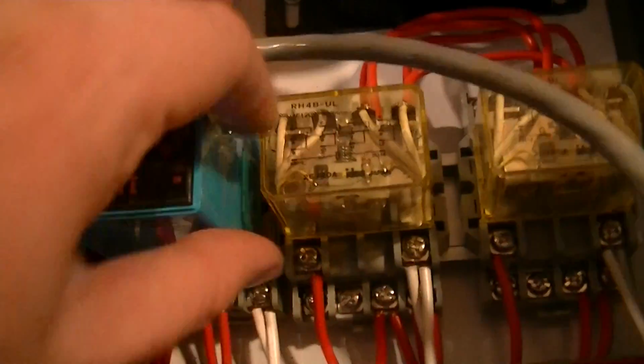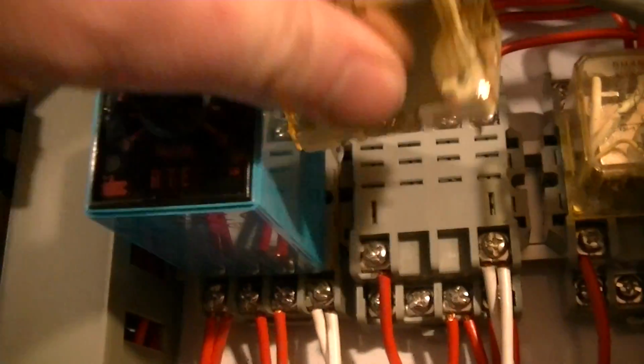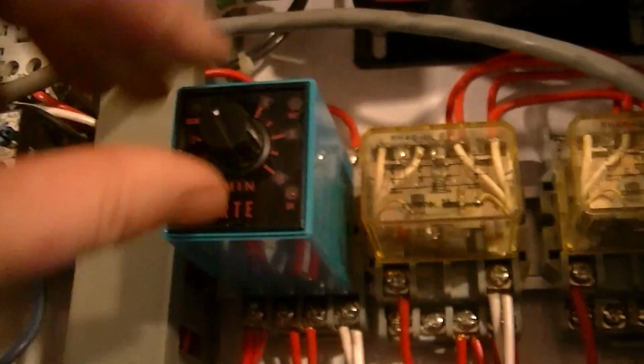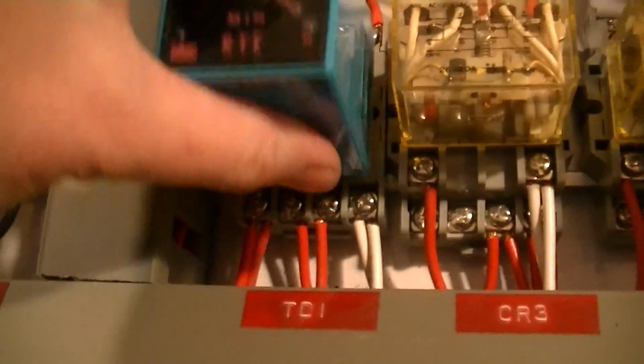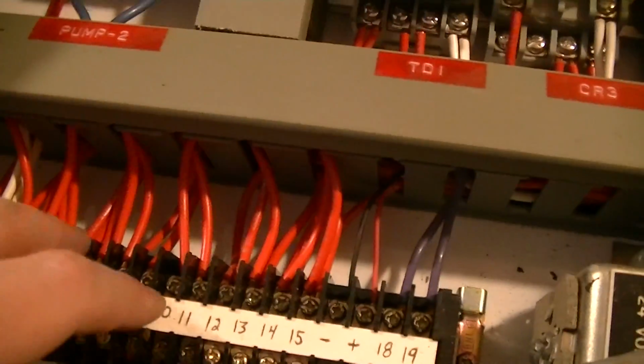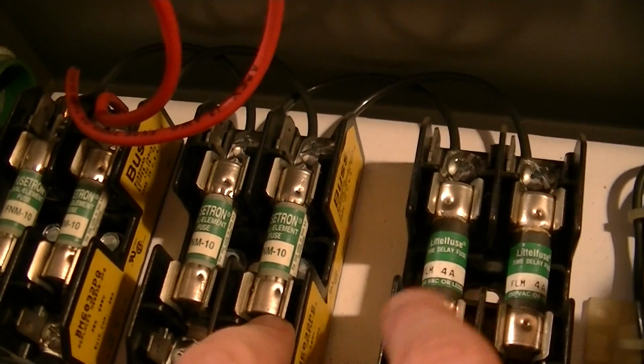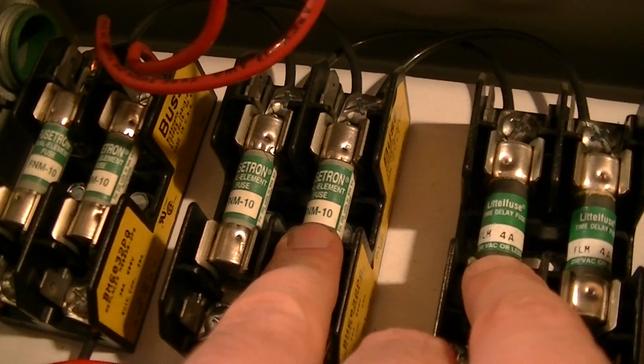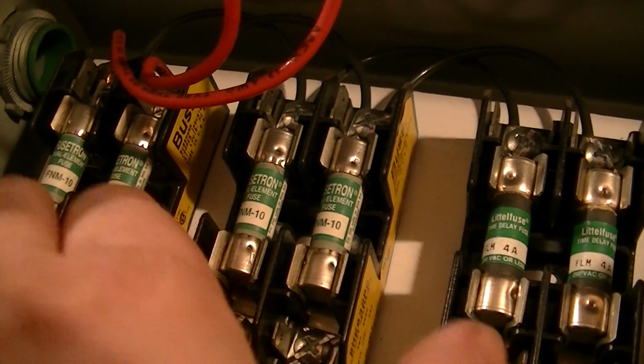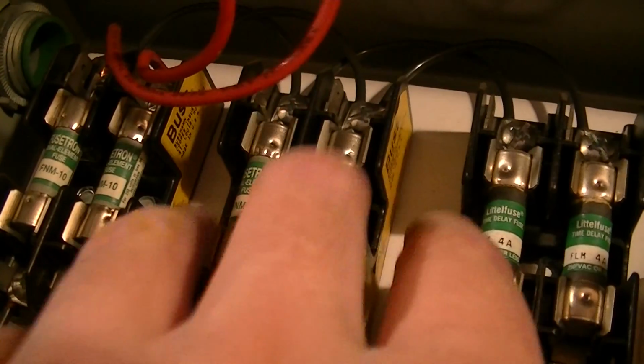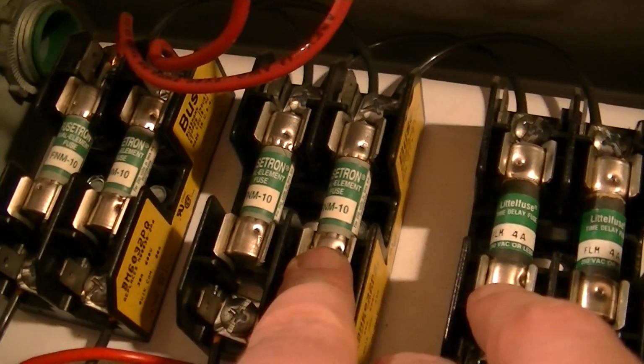And then of course there's a pair of regular, conventional 4-pole, double throw, 120 volt relays. That one's also 120 volts, but it's octal based. And it's also got a little terminal strip, which are quite useful. And fuse blocks. So these are fairly standard midget fuses, and whoever put these in was intelligent. And also, you wouldn't ordinarily be doing this because it'd be 208 volts between all these terminals. This is a 208 volt single phase controller, by the way.